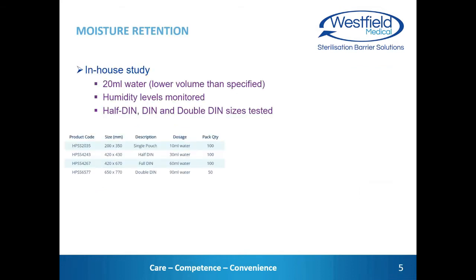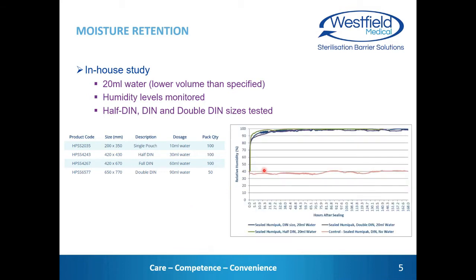To illustrate the effectiveness of moisture retention, we devised a test which actually used a smaller volume of water than specified for the pouches to show how effective the moisture retention is. We placed a humidity data logger inside a pouch along with a polypropylene container to create an airspace, as it would be if there were a tray or instrument set inside, but which itself doesn't contribute to the humidity levels. We then added 20 millilitres of water and sealed the pouch. We stored that for 1 week, along with a control sample which contained no water at all. This was really just to give us a base level of the humidity that's expected just through normal temperature variation without the addition of the water into the pack.